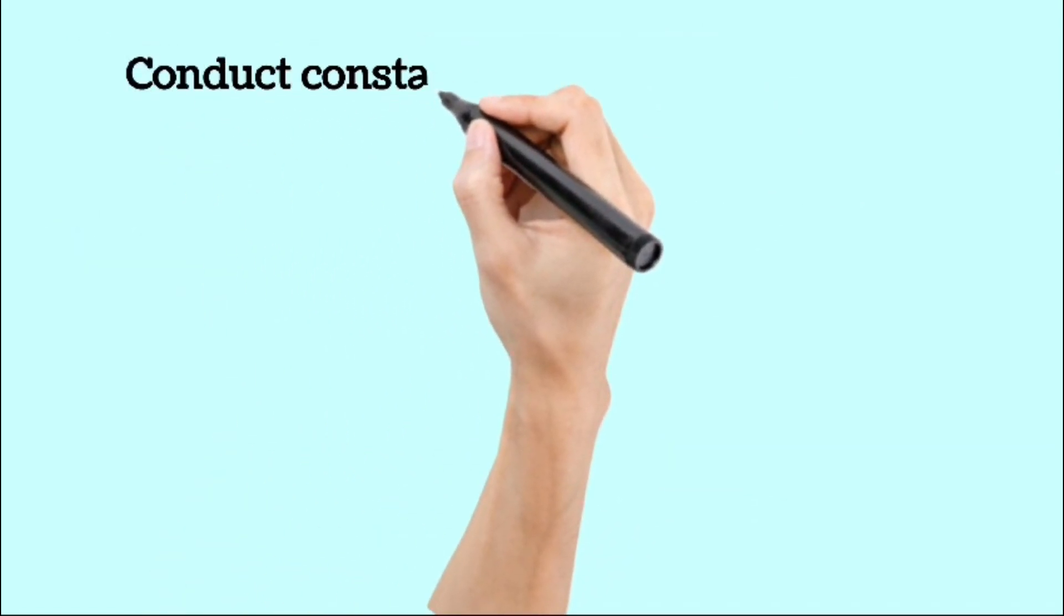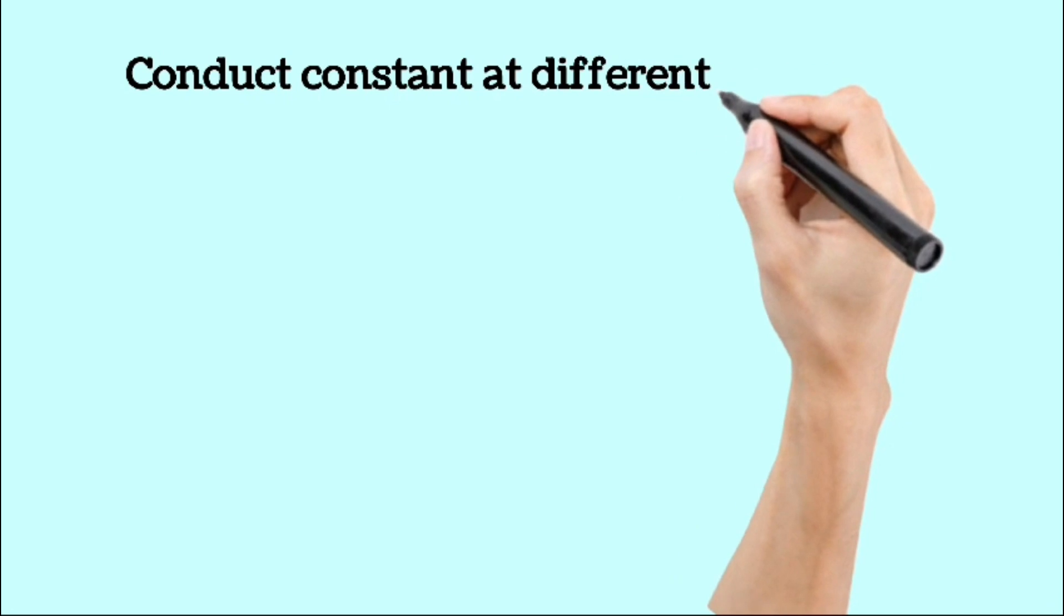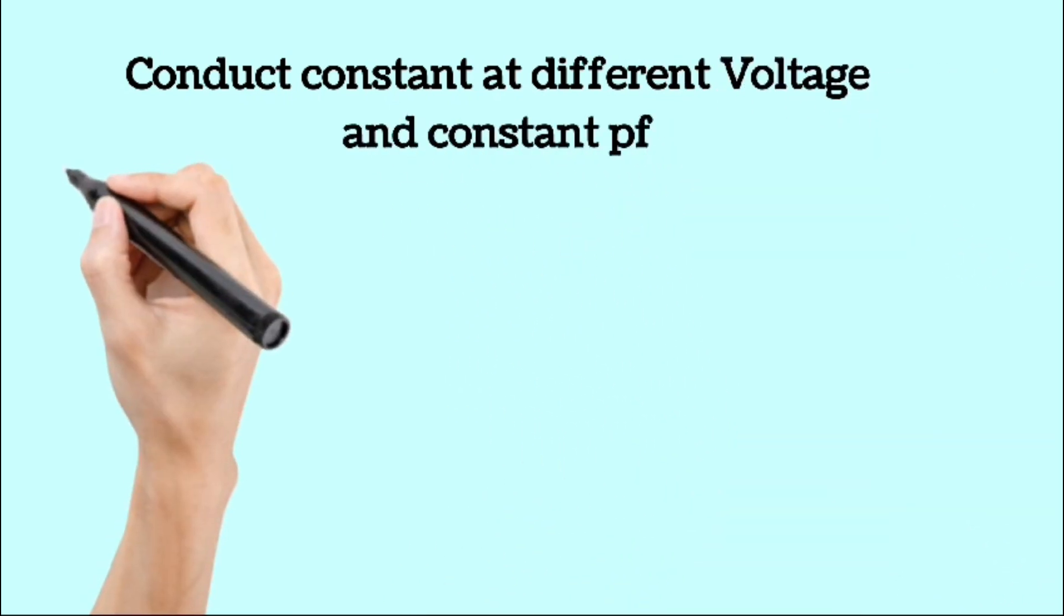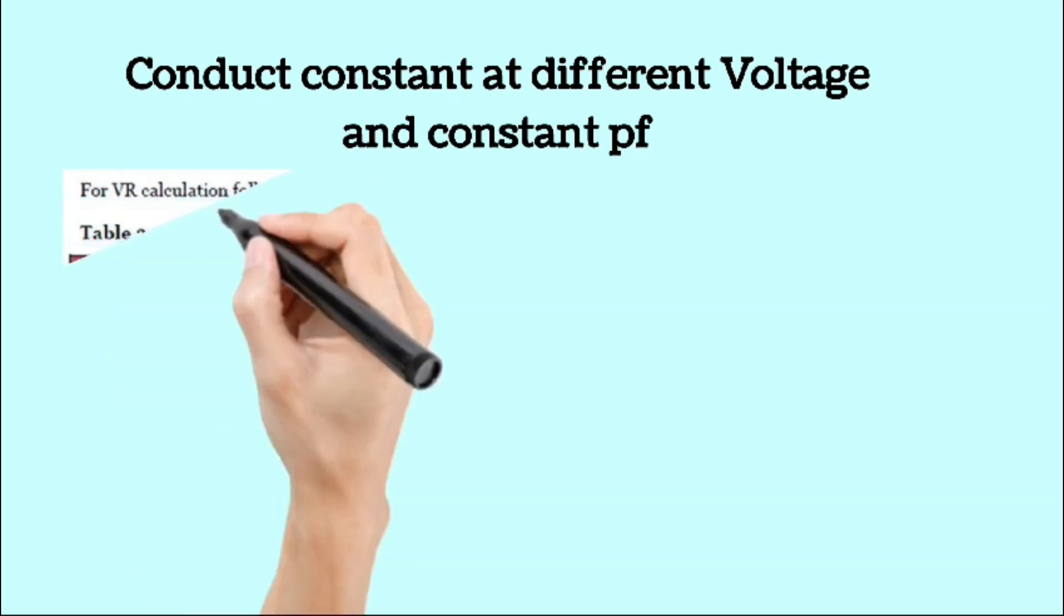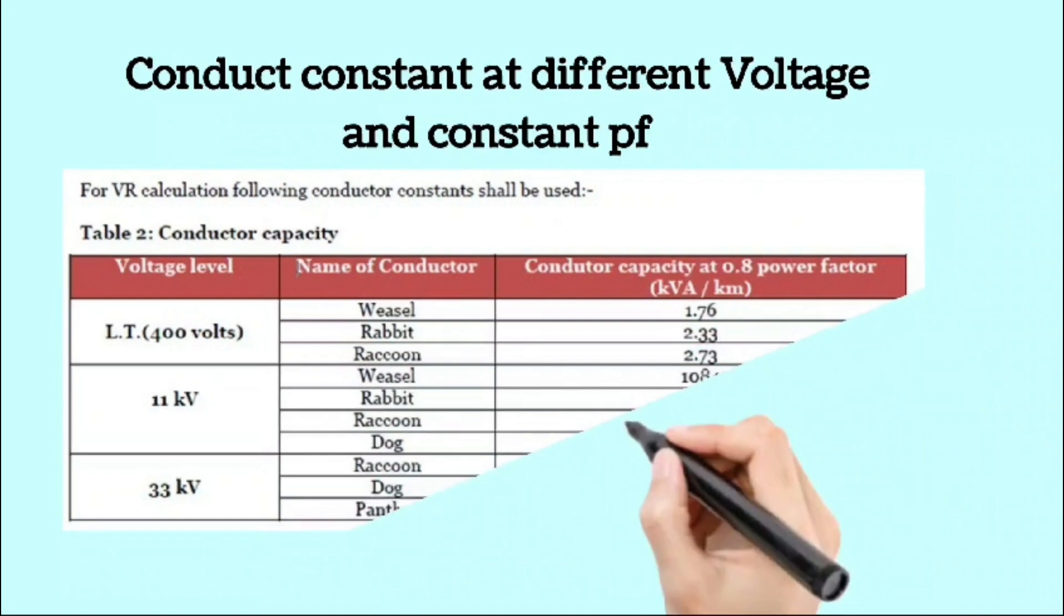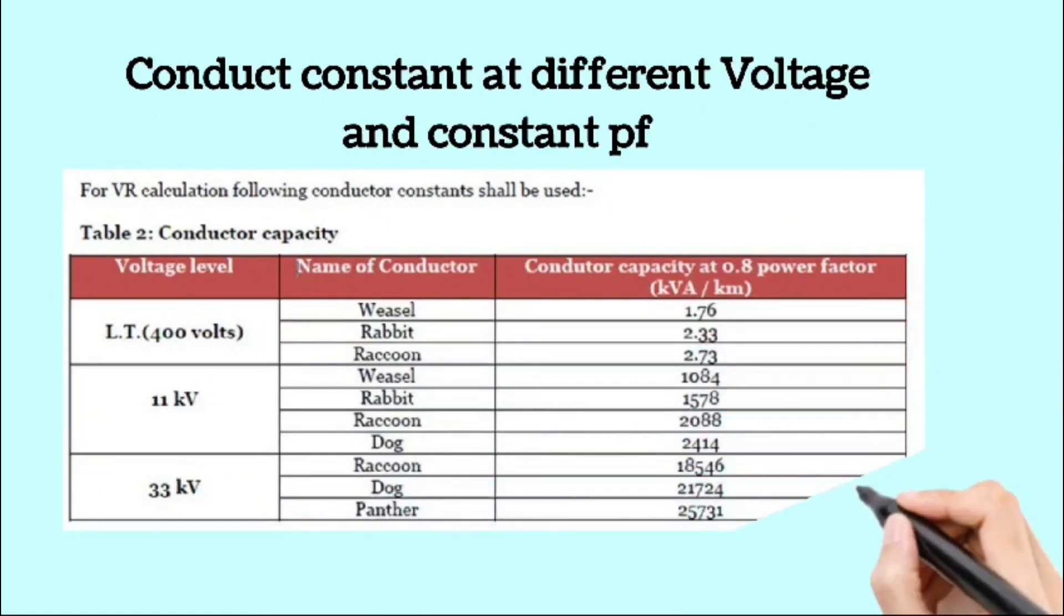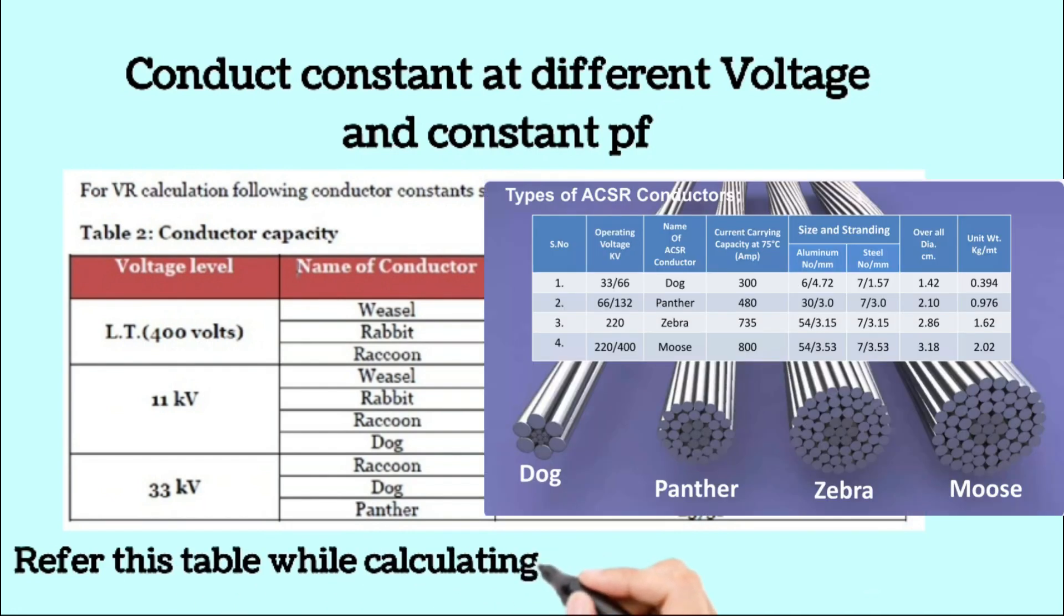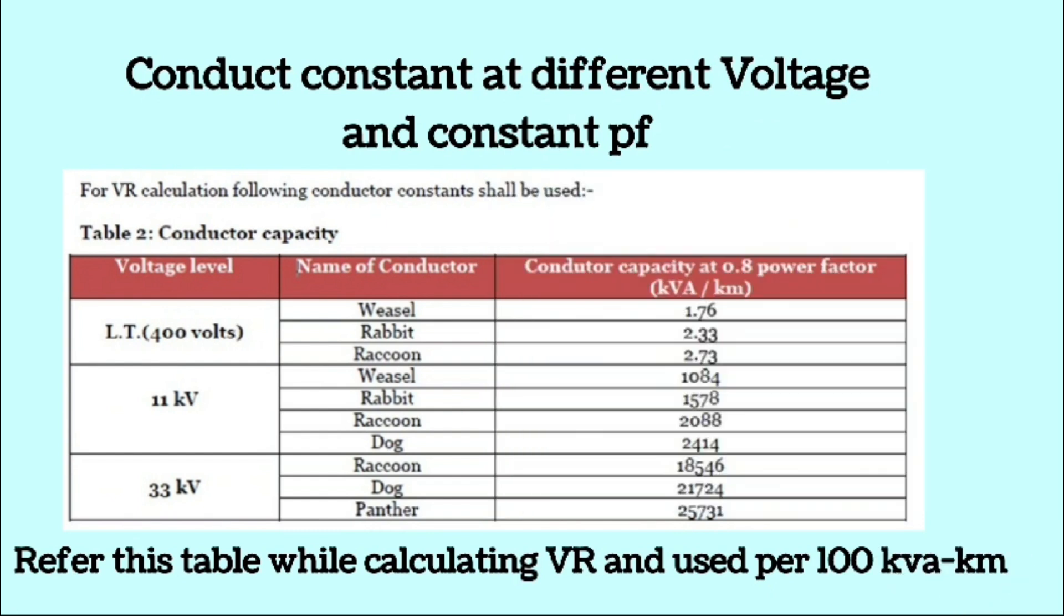In the next step, a table is provided. This table contains the values of conductor constants in kVA kilometer for different types of conductors at various voltage levels and a constant power factor of 0.8. For future reference, this table should be referred to when calculating voltage regulation. It is important to note that the regulation constant depends on the current carrying capacity of the conductor and the length of the line.